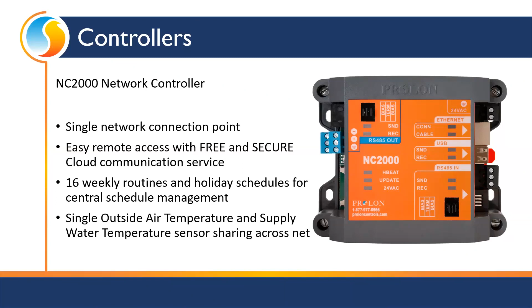Also, because the network controller ties the system together, we are allowed to use a single outside air temperature sensor and a single supply water temperature sensor shared across the network. That saves us from having to put outside air temperature sensors on every single unit; we can distribute that through the network. Same thing with the water supply, we can get it from boilers, from chillers, or out of one of those Flexios, and say to all the units using water to heat and cool, here's the temperature coming to you.